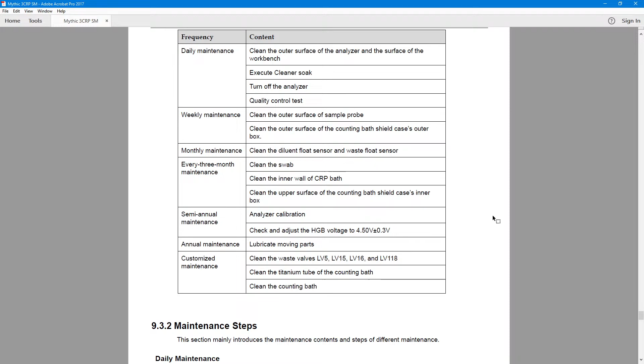Weekly, you also need to clean the outside surface of the sample probe. Clean the outside surface of the counting bath shield case outer box. So what is that? Let's go to this page. It means to clean, especially in those areas on the top, because there will potentially be a little bit of salts. So those things need to be cleaned.